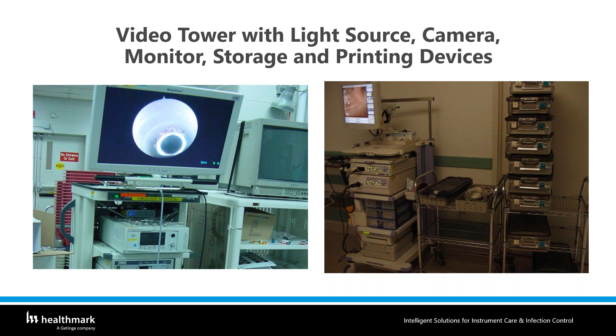When Stryker and Arthrex were talking about an endoscope, it was literally that you take one of your video towers in your operating room or medical procedure unit, and take one of the endoscopes, usually 2.7 to 3 mm, to look inside those shavers. So when we received a letter from the FDA, we had to go borrow one of these towers, which is about, as you know, $250,000. And we couldn't bring it down to SPD. We had to take our trays up to the OR and try to do that. These are patient-ready trays that had that arthroscopic shaver within them.